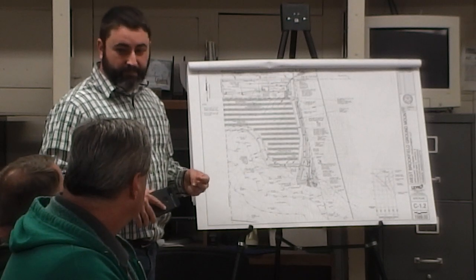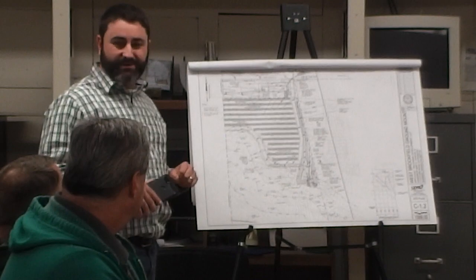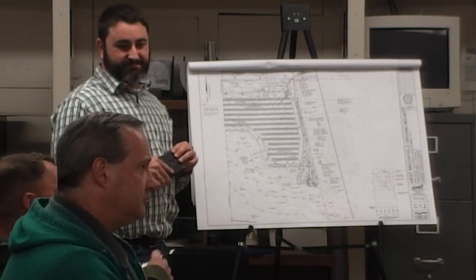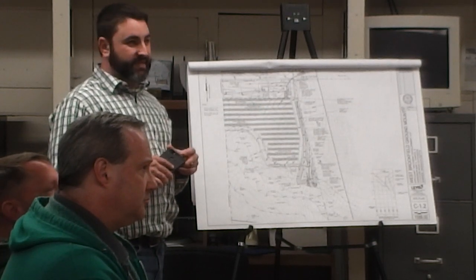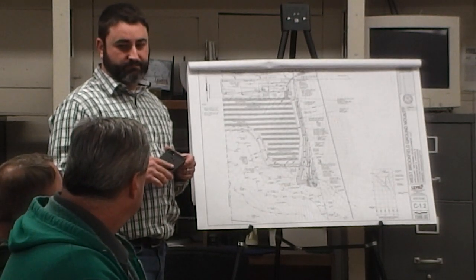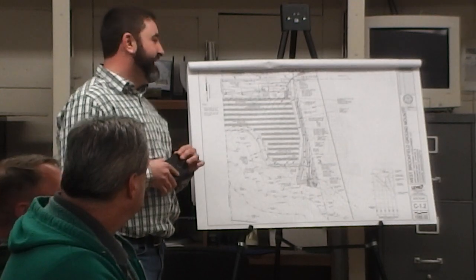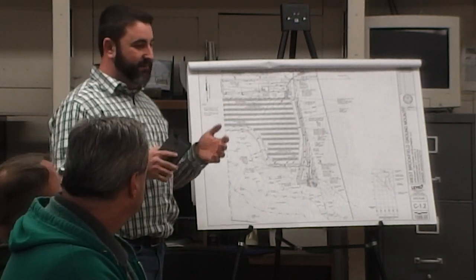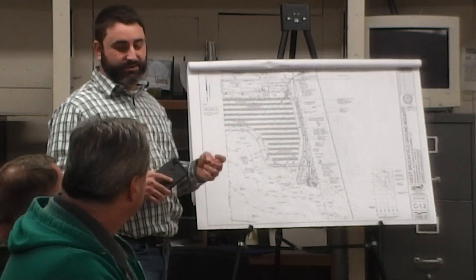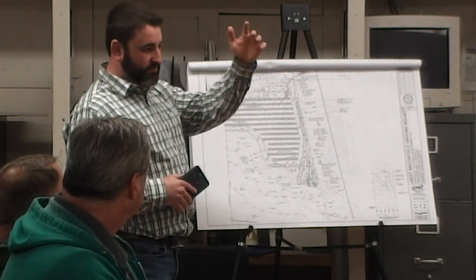So you have a fire suppression system inside there? 100%. I learned about that on the conference call with Con Edison. The system suppresses the air and takes the oxygen out of the container, so it suffocates the fire. It's great for fires, but if you're caught in there, you're dead. That's why it's a sealed container, and it's good for electronics, so for the batteries. If there was an issue, it's remotely monitored, and they went through the levels of alarms.